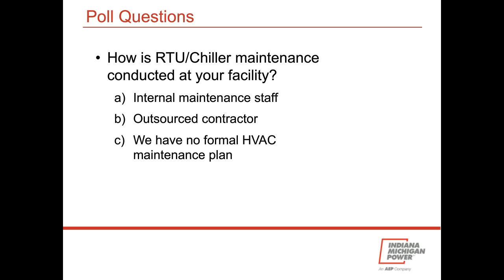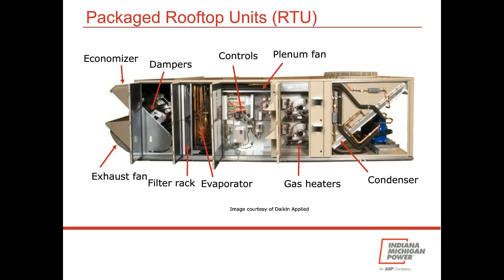While you're filling that out, we'll move forward and start our discussion of packaged rooftop units. And just what is a RTU, as we call it? Well, ASHRAE's definition says it's unitary cooling equipment: one or more factory-made assemblies that normally include an evaporator or cooling coil and a compressor and condenser combination. The units can perform a heating function as well, and you'll see that here in the different pieces and parts inside this packaged unit. It's often just lifted up on top of the building. It's interesting that 1/3 of all commercial buildings have packaged rooftop units, and that represents cooling of 50% of commercial floor space. So they're pretty darn ubiquitous. I'm sure many of you have those as well.